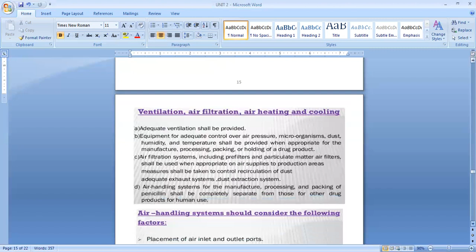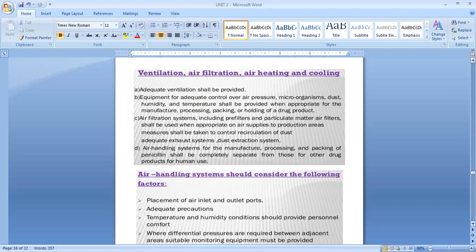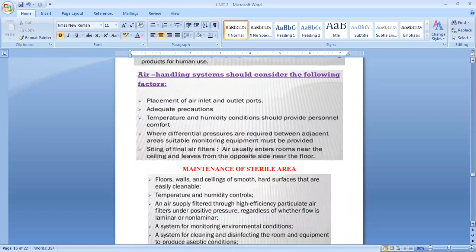Air filtration systems, including pre-filters and particulate matter air filters, shall be used when appropriate on air supplies to production areas. Measures shall be taken to control recirculation of dust, with an adequate exhaust system and dust extraction system. Air handling systems for the manufacture, processing and packing of penicillin shall be completely separate from those of other drug products for human use.